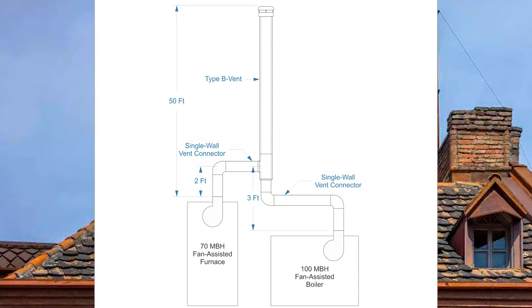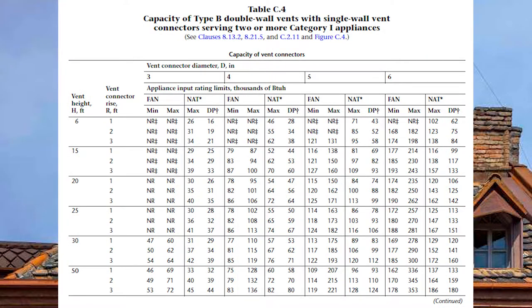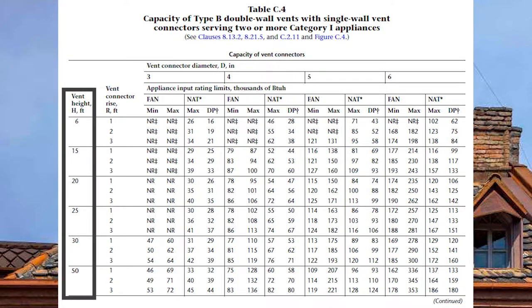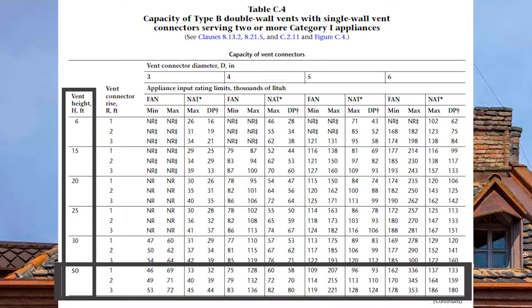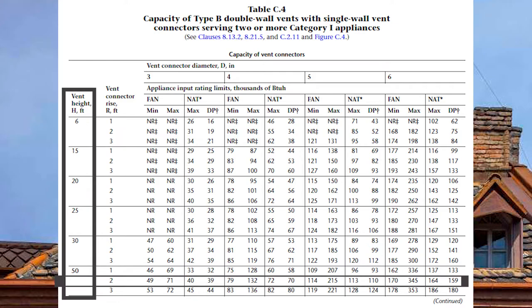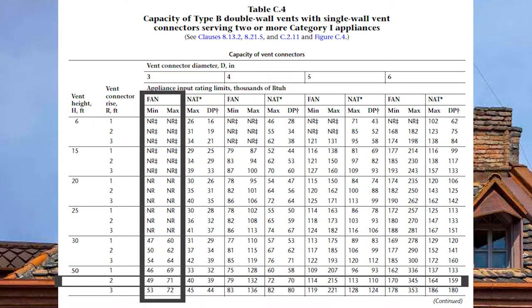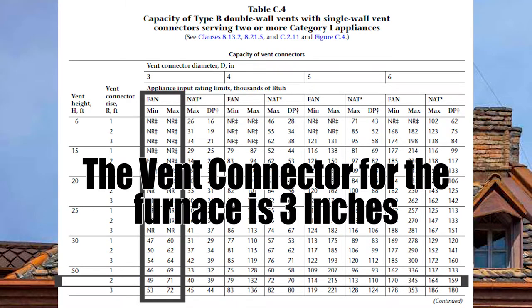Turning to page 204 in the gas code to table C4, I come down on the left-hand side for a vent height of 50 feet and start with the fan assisted furnace which has a vent connector rise of two feet. A three-inch vent connector fan min-max is good between 49,000 and 71,000 BTUs — perfect for our furnace. So we will have a three-inch vent connector serving the furnace.